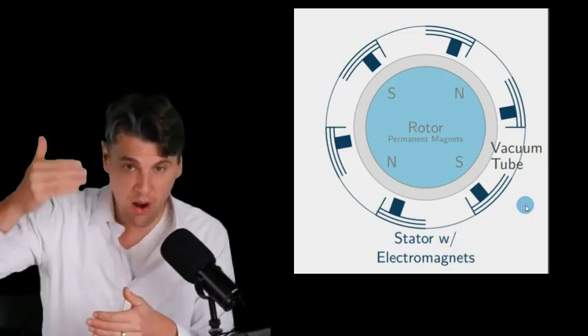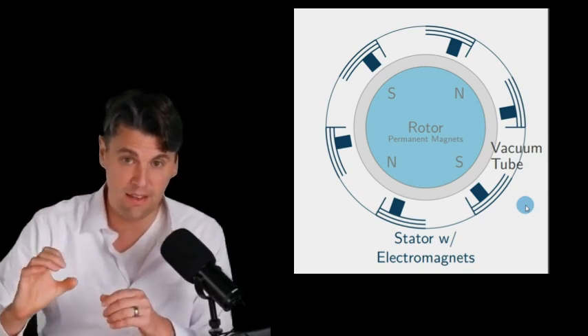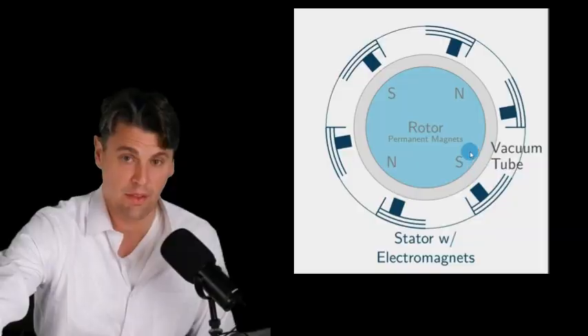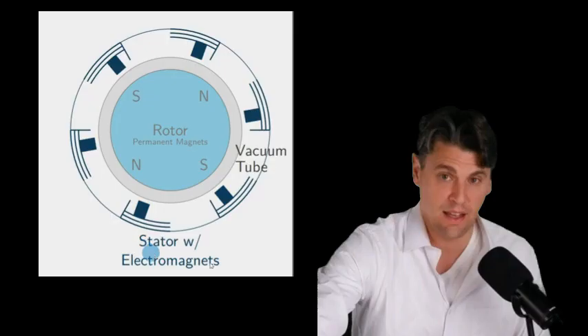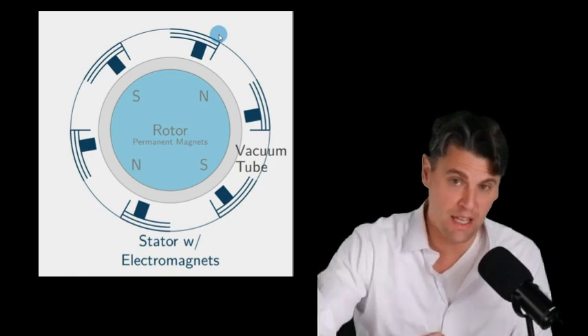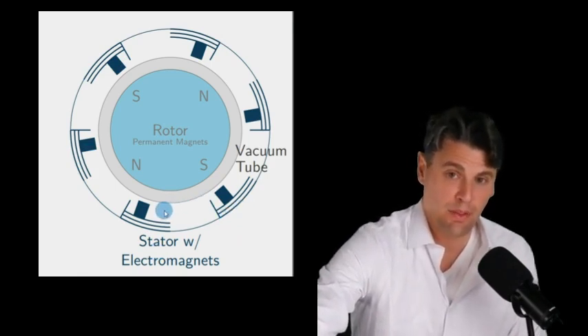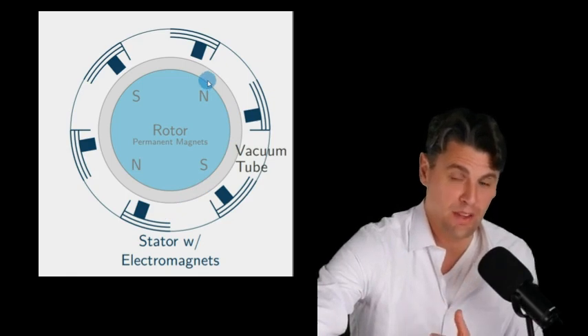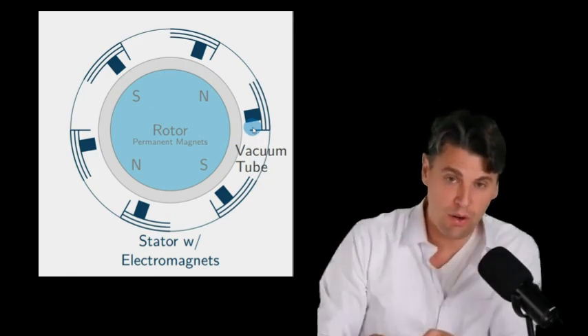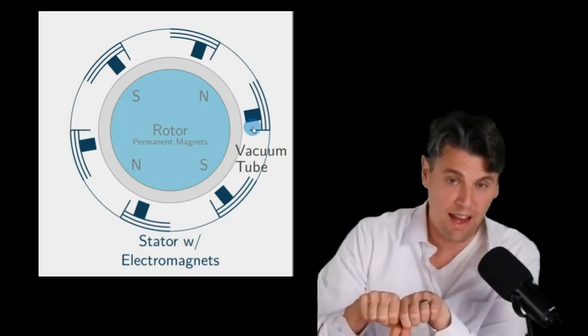As far as that motor, this is a cross-section of how an induction motor works. The rotor on the inside and the stator on the outside. And the rotor is just a permanent magnet. So you can think of it having north-south, north-south, different poles here. And then outside is what we call the stator. This is stationary. Even though it's a stationary set of electromagnets, they actually change in time. We have an alternating current coming in, and we actually are changing in time the magnetic field at each of these magnets so that if you think about one little north pole here, it will get pulled to one electromagnet. And then we'll change the field so it'll get pulled to the next electromagnet. We'll change the field again so it'll continue getting pulled. And so that is what's going to cause our rotor to rotate. And that rotor is hooked straight to that anode inside of our x-ray tube.